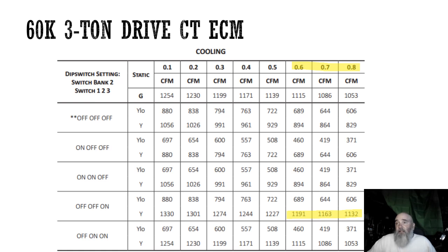So we got a 2.5-ton air conditioner and you have a high sensible heat ratio. 1100 CFM might be your target. You could have an external static pressure of 0.8. Now, that's not only for use as to confirm that you actually have the airflow in the system that you may be designed for. Speaking of design, we would be starting off at 0.8, and then we would be deducting things like an evaporator coil, a filter, a bunch of other stuff that potentially is going to ultimately allow us to solve for what our available static pressure is.